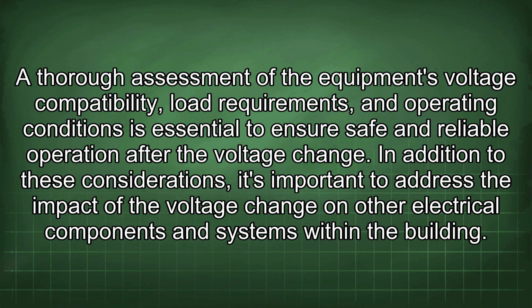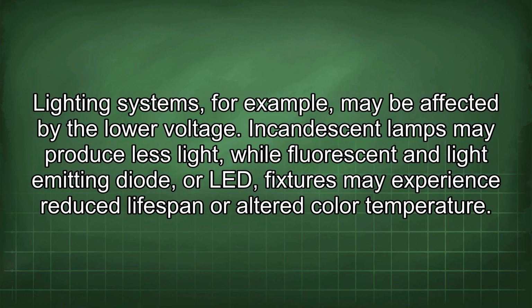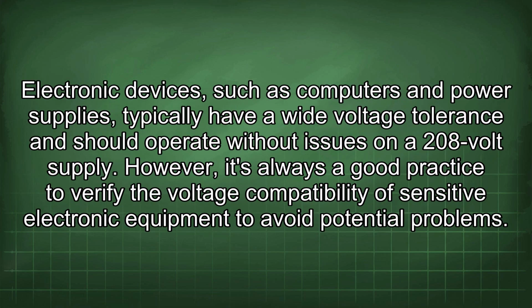In addition to these considerations, it's important to address the impact of the voltage change on other electrical components and systems within the building. Lighting systems, for example, may be affected by the lower voltage. Incandescent lamps may produce less light, while fluorescent and light-emitting diode, or LED, fixtures may experience reduced lifespan or altered color temperature. Electronic devices, such as computers and power supplies, typically have a wide voltage tolerance and should operate without issues on a 208-volt supply. However, it's always a good practice to verify the voltage compatibility of sensitive electronic equipment to avoid potential problems.